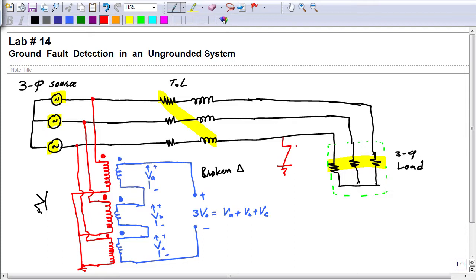The reason is that in the presence of this ground fault, if another ground fault occurs, that will result in a line to line fault. That's why sometimes, even in an ungrounded system, detection of ground fault is required. Once a ground fault is detected, tripping is not necessarily required. The relay may just activate an alarm that grounding has occurred. Now let's see how this mechanism helps us detect the ground fault in an ungrounded system.